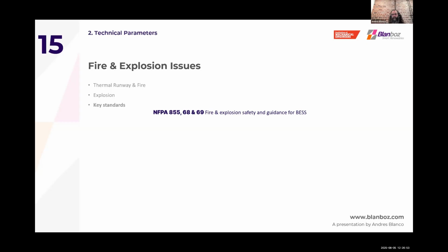Currently, we have the 2023 version of the NFPA 855, which is being revised, and the new one is coming next year. The 2023 version gives you as optional either the 68, which are your little vents that I showed you in the previous slide, whether forced or natural ventilation, or having computational fluid dynamics design analysis done on your system. The new version is actually going to make it mandatory that you need to have forced ventilation and you need to do your CFD analysis on your system.